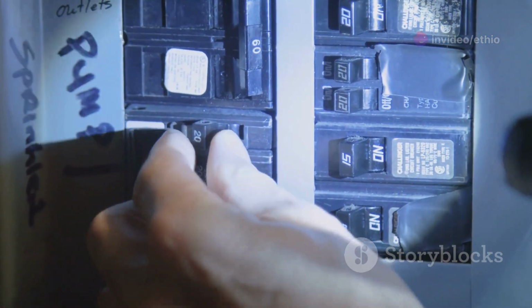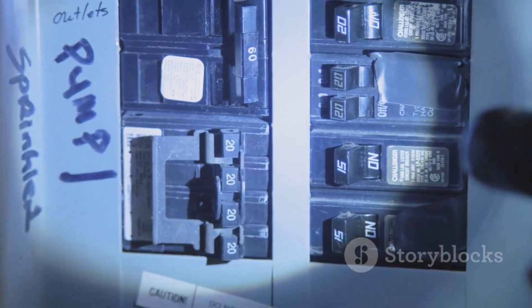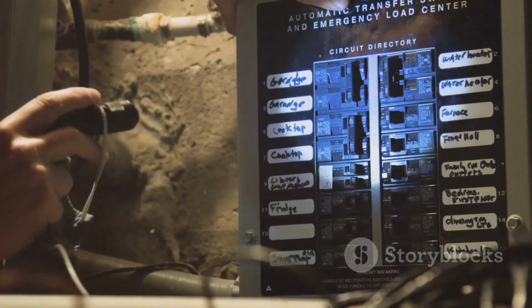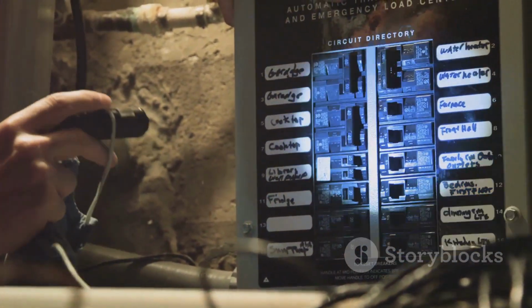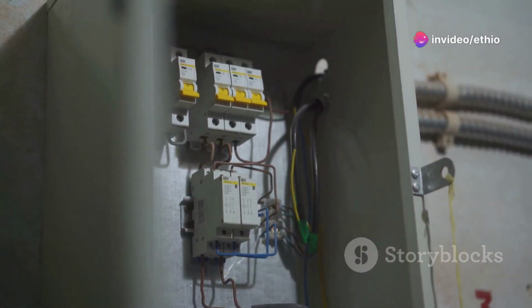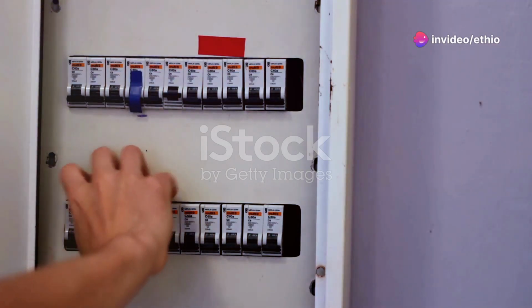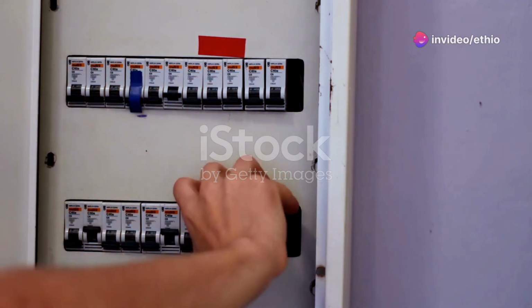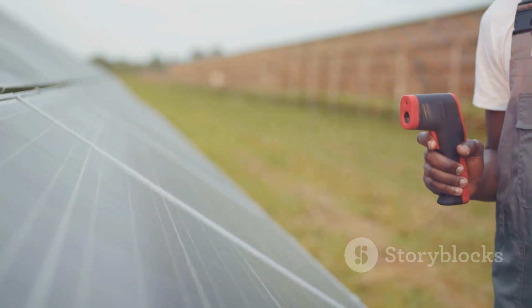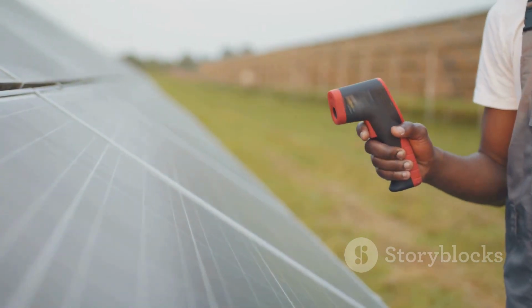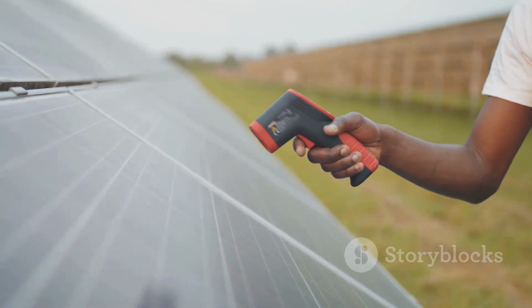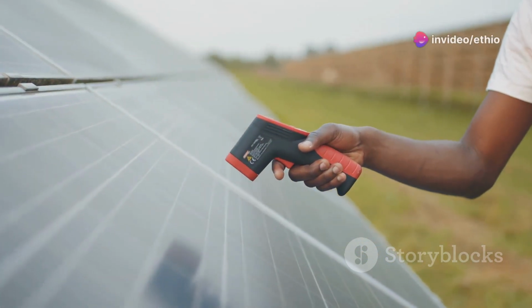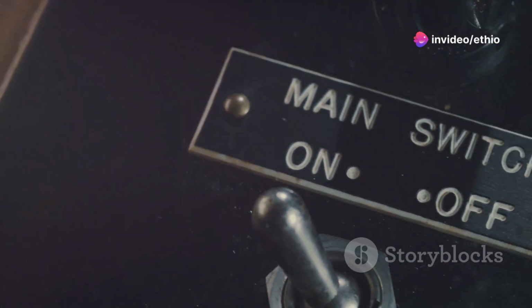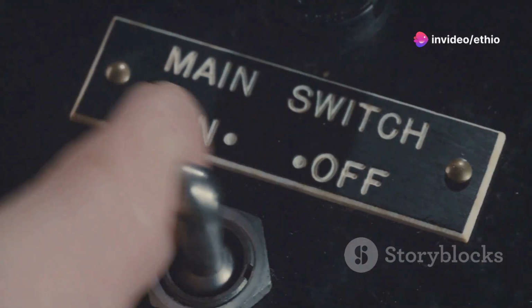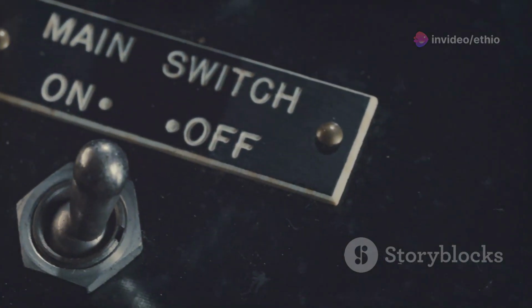Next, head over to your electrical panel and take a good look at the circuit breakers that control your solar system. Are any of them tripped or sitting in the middle position instead of fully on? If you spot a tripped breaker, just go ahead and reset it by flipping it all the way off and then back on again. Then, check the DC isolator switch, which is usually located near your solar panels or inverter. Make sure it's fully switched to the on position. Sometimes it can look on, but not be fully engaged.